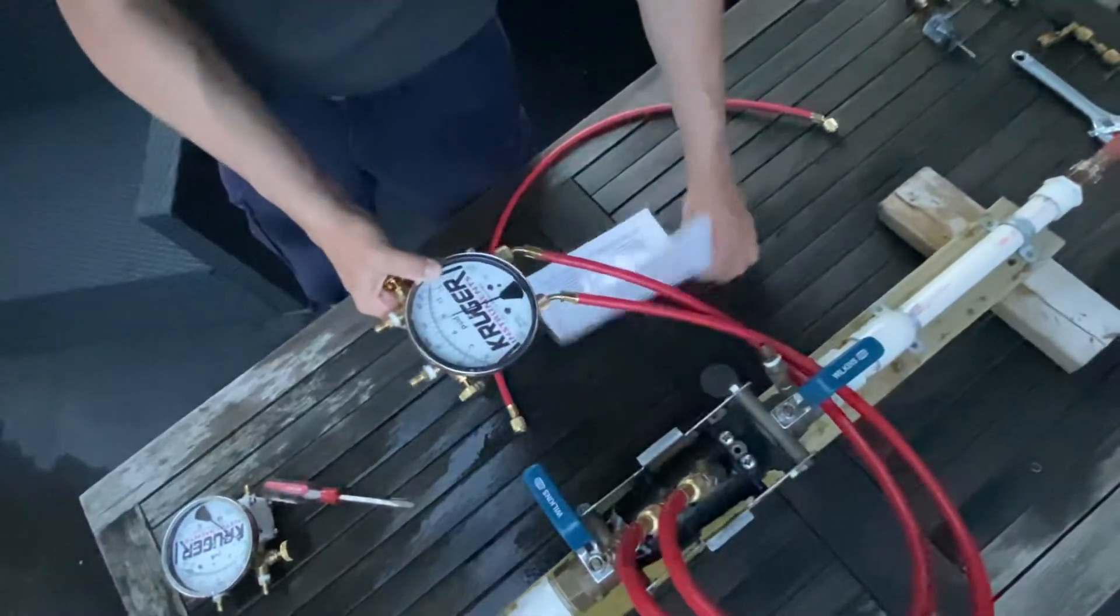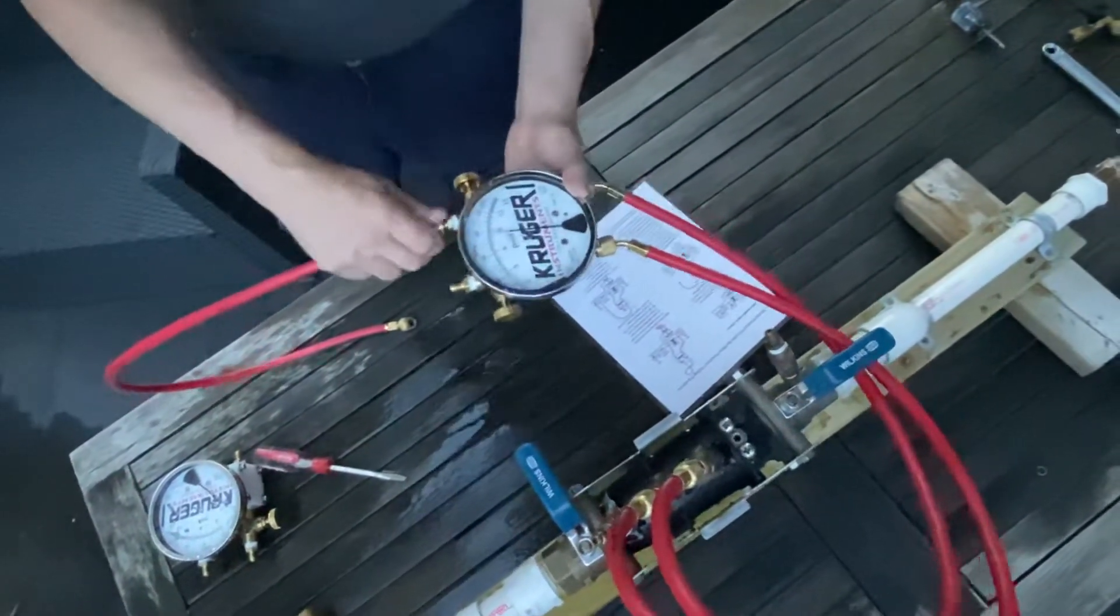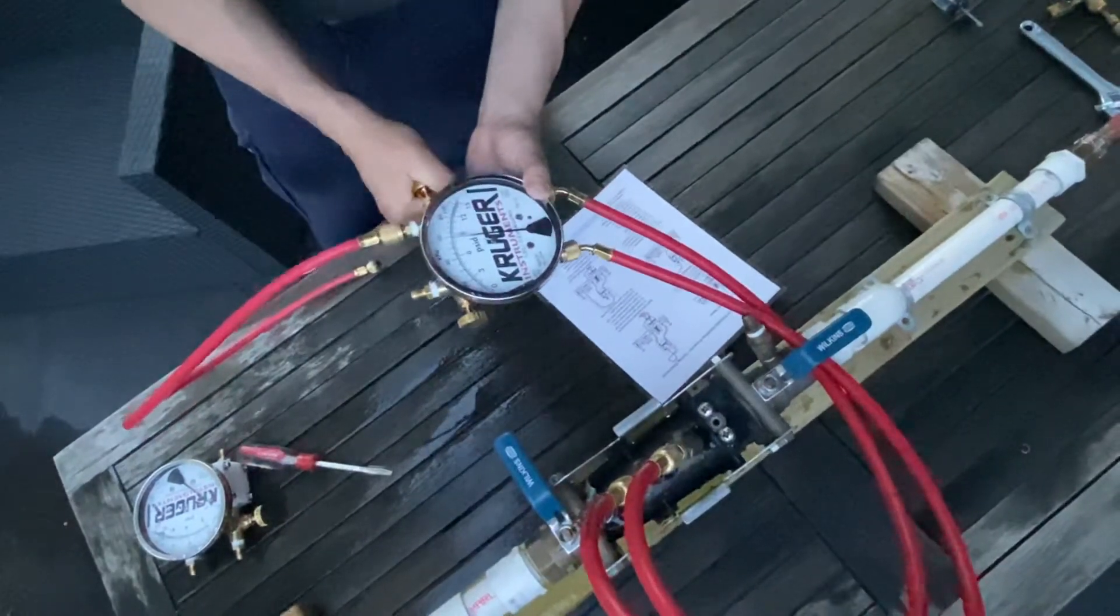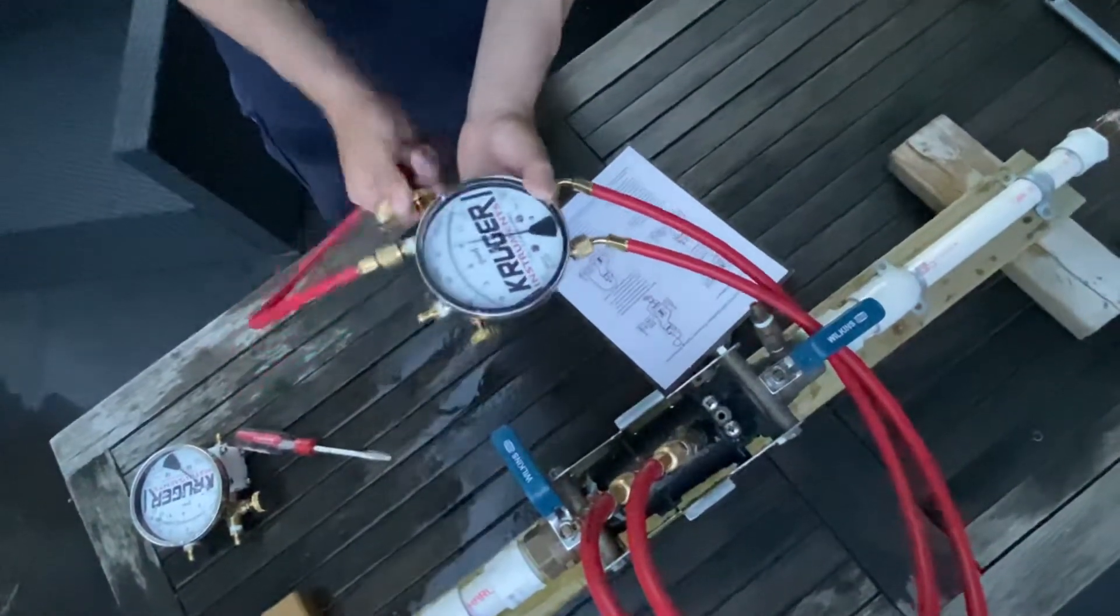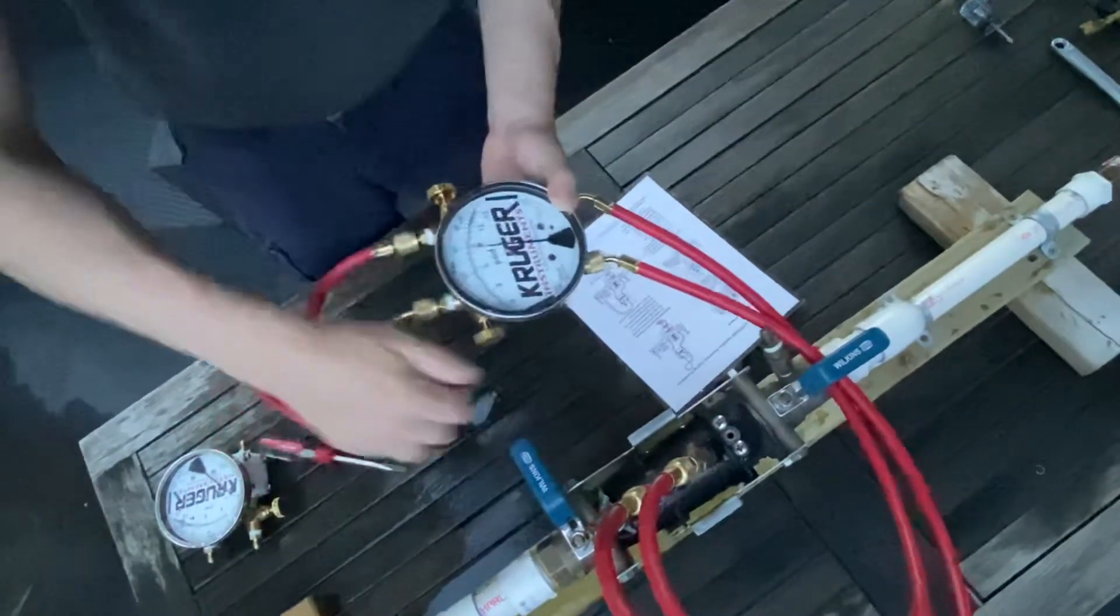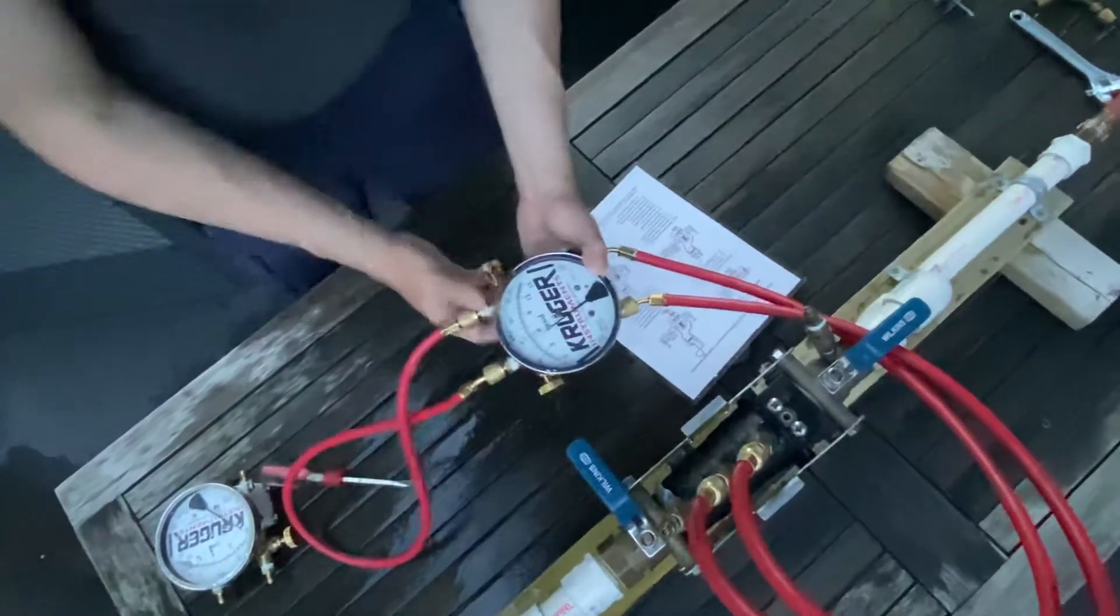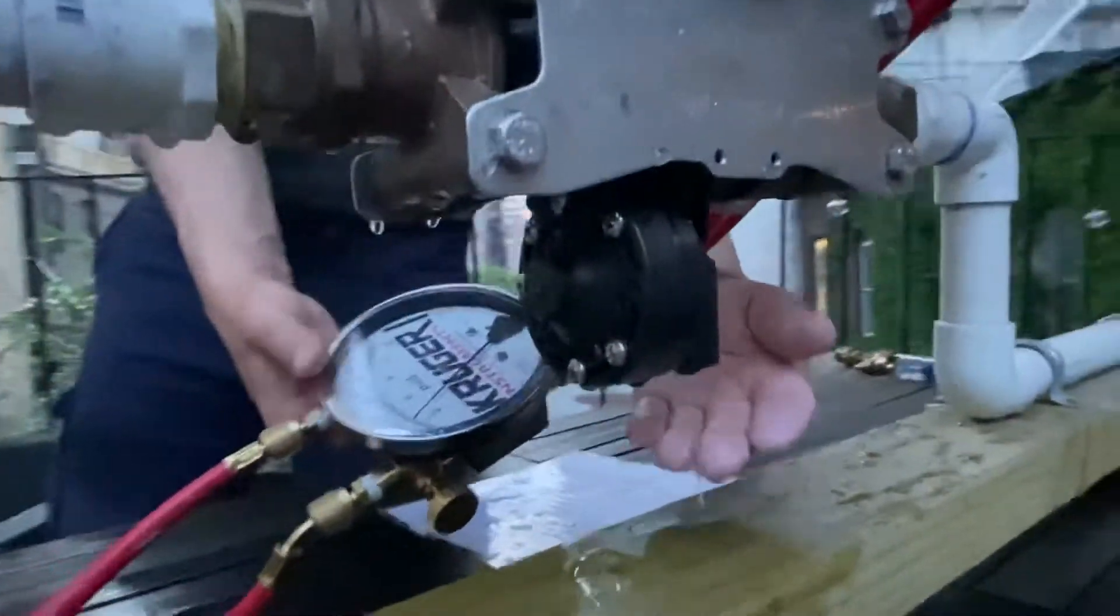So the first test is the relief valve opening point. You attach another hose to the low side of the kit, open low bleed, you bleed the water through, close low bleed. Attach the other side of the hose to the high side of the kit. Open high valve one full turn, open low valve a quarter turn. You'll see the pressure going down. Then you put your hand under the vent and when you feel water coming out, that's your relief valve opening point. So 3.6, has to be at least two.